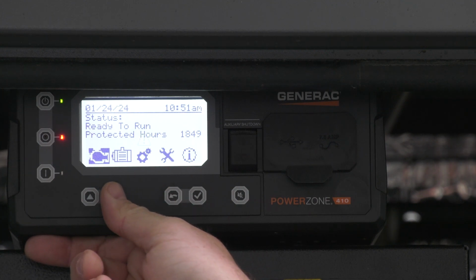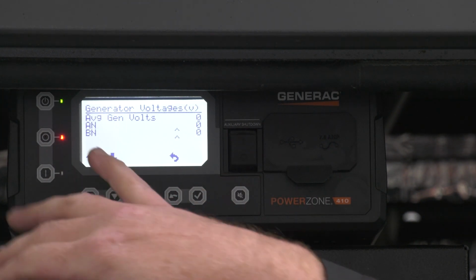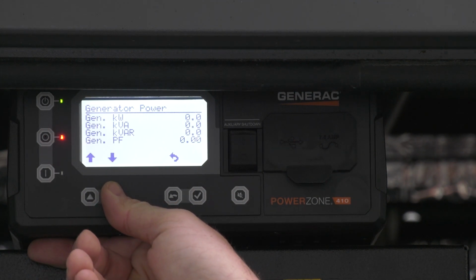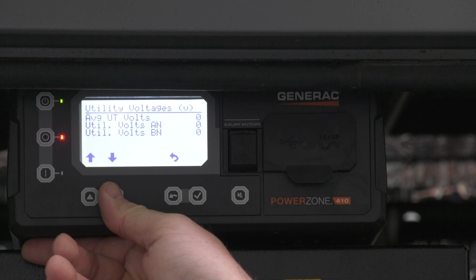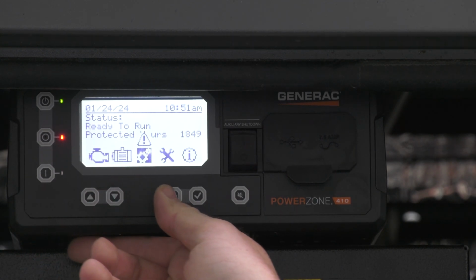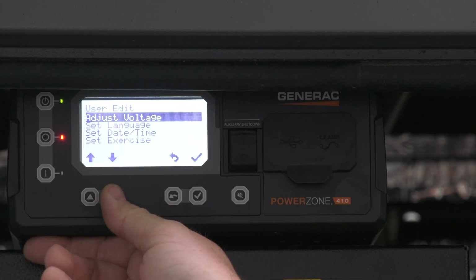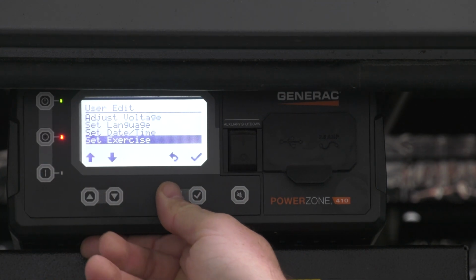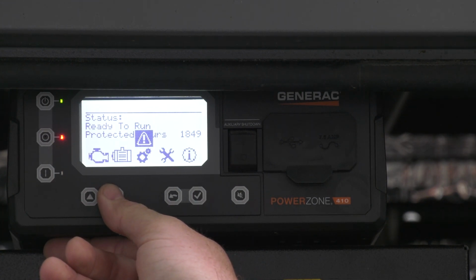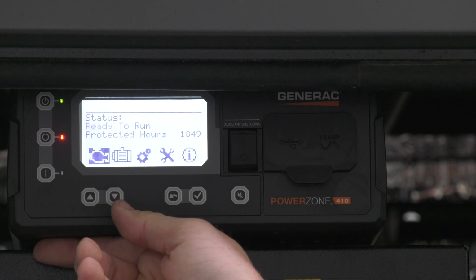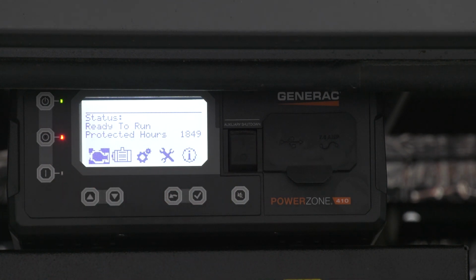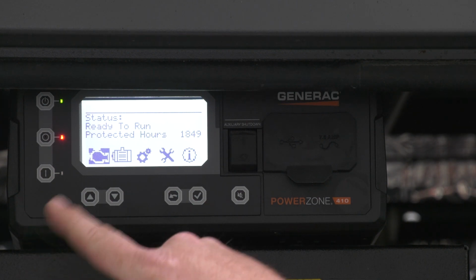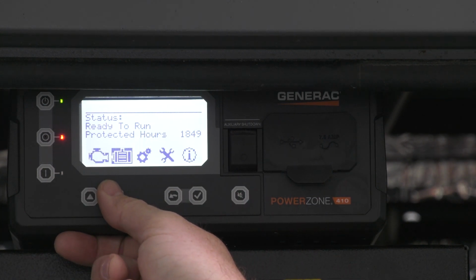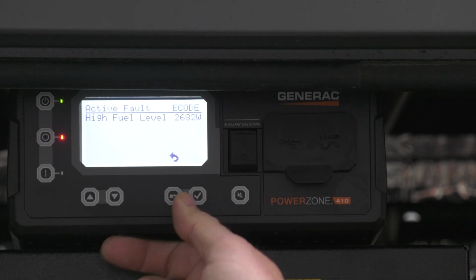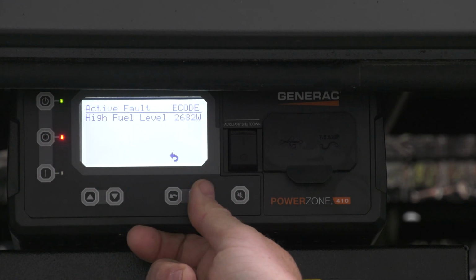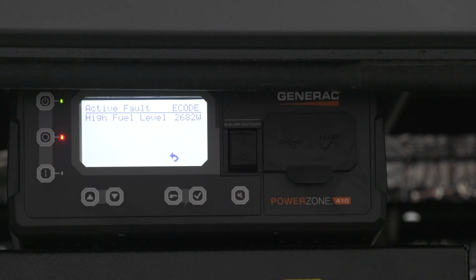Hit the back button, scroll over again, you'll get generator information, you'll get your voltage, your amps, KW, all the information on that side. Hit your back button, go over again, you'll go into settings, which is stuff you can't really mess with without a code anyway. The biggest thing would be alarm clearing. Like right now, it's got a high fuel because that cannot be cleared until the fuel runs down. Right now, it's in alarm. That's why you have this flashing. You have to scroll over until it highlights it, hit your check, so you'll have high fuel level. And you can hit the check again, and if it's something that's not latched, it'll clear.